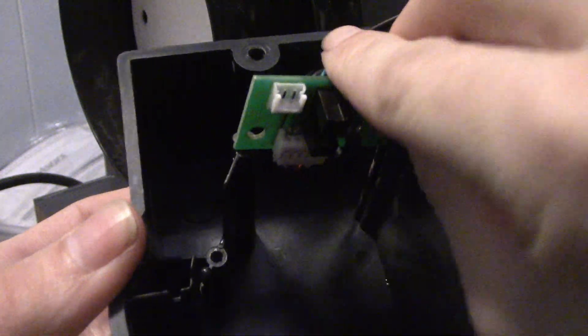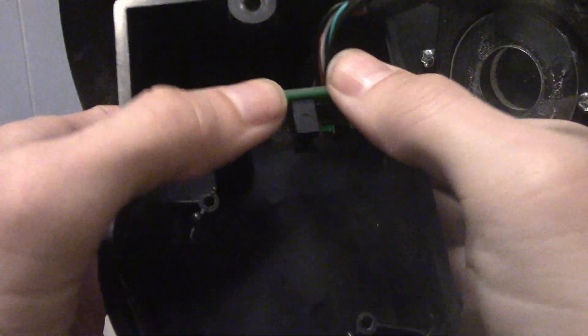Take command of the silicone plug once it appears inside the unit. Run the plug horizontal to the damper rod and fasten together with the pre-existing tape, or replace it with the new tape provided. Step 16: Take the electronic board and secure it to the new damper casing. Use medium force to slide the electronic board down the tracks.